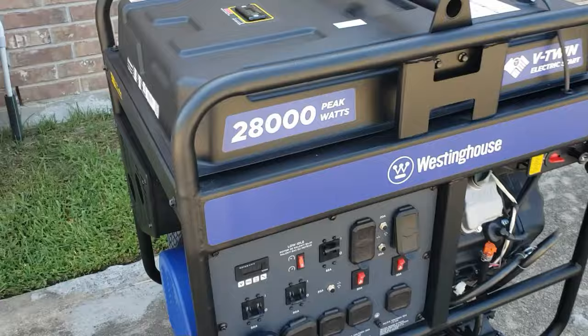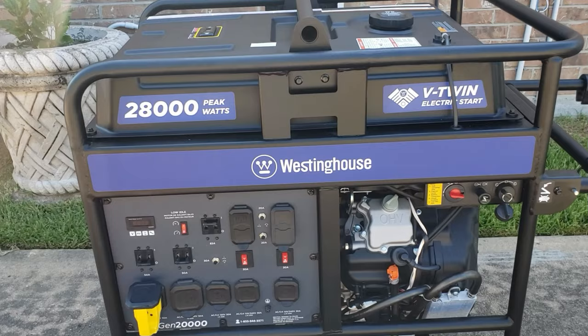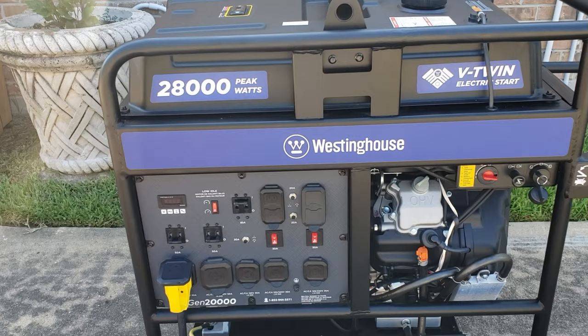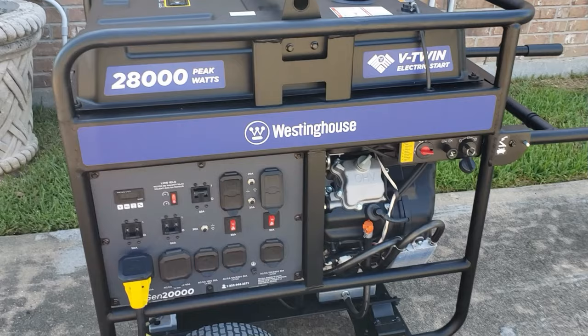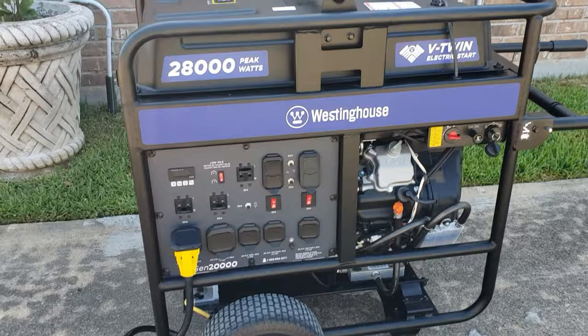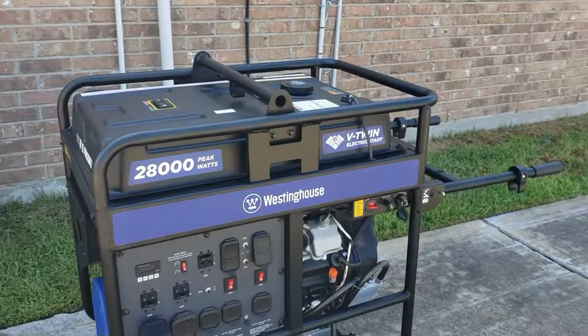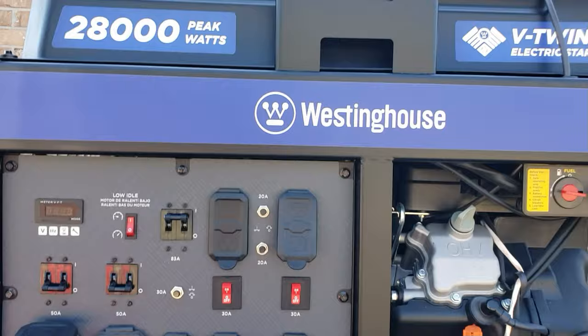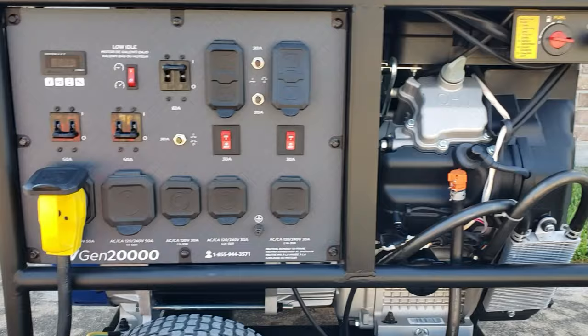We just tested the WGen 28,000 watt peak on my entire house. One thing I noticed is when this thing is running and the AC comes on or a heavy load comes on, there's absolutely no change — that's a pretty good sign. It runs right about 77 dB, and when it's on eco mode it goes right about 69 dB. It's not a very loud generator for what it puts out. Next time I'm going to try to power the entire house and an RV. This thing can power the entire house with absolutely zero issues. Thanks for watching — please subscribe, give a thumbs up, leave a comment, and more testing to come!